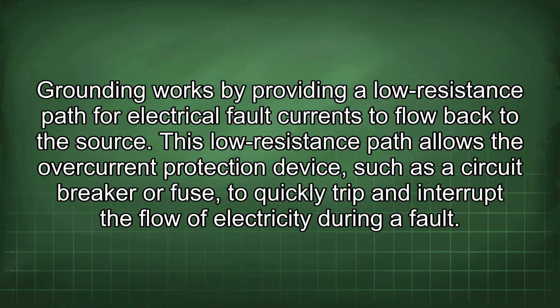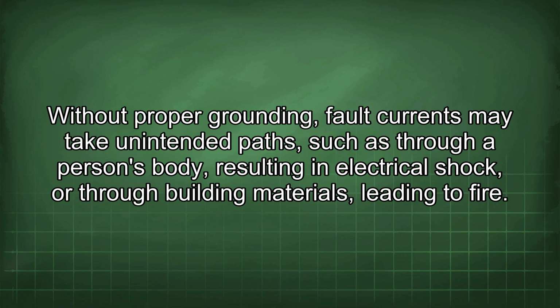Grounding works by providing a low-resistance path for electrical fault currents to flow back to the source. This low-resistance path allows the overcurrent protection device, such as a circuit breaker or fuse, to quickly trip and interrupt the flow of electricity during a fault. Without proper grounding, fault currents may take unintended paths, such as through a person's body, resulting in electrical shock, or through building materials, leading to fire.